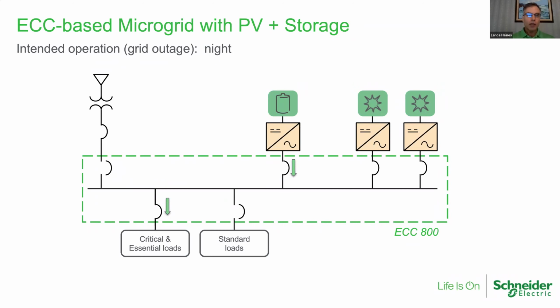So here with the grid outage, one thing to notice right away is on the left-hand side, inside the dotted green line representing the ECC, the main breaker is open. That's how we're able to isolate the site's electrical system from a grid that is down - the microgrid control system automatically opens that breaker to begin the islanding.